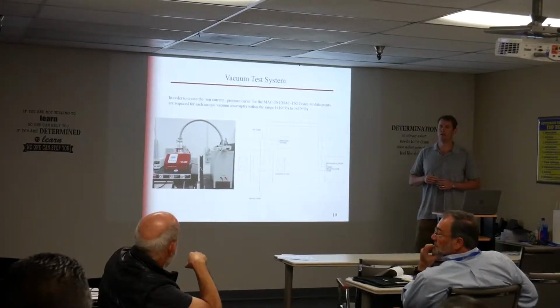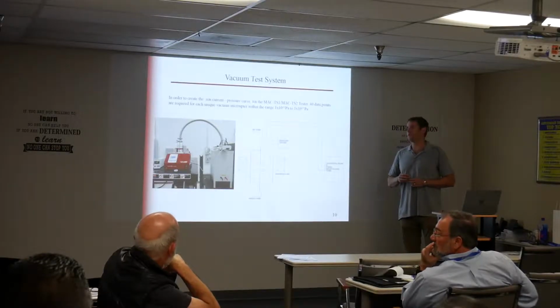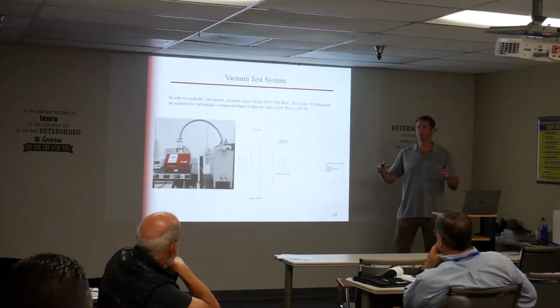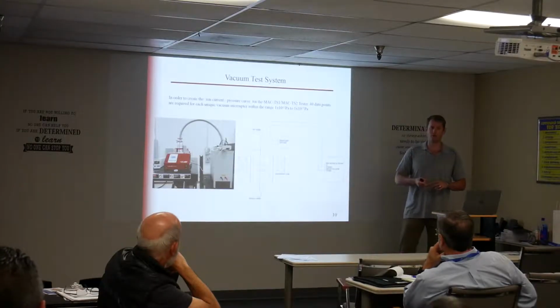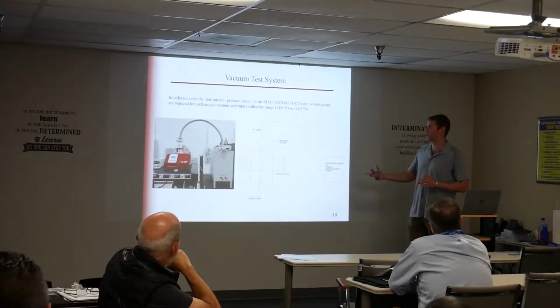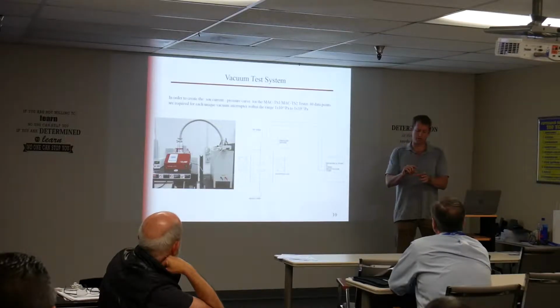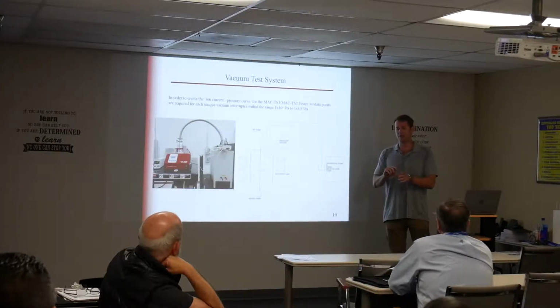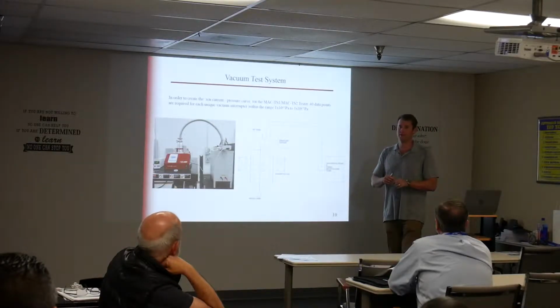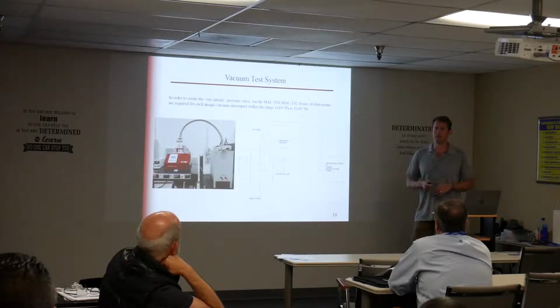In general, can you tell how old an interrupter is based on the characteristics you measure? Yeah. The size of interrupters are getting smaller and smaller because the materials, clean rooms, and manufacturing process have improved, because obviously the '80s, that was the first shot at it. And these were big glass bottles made by hand, and they have pinch tubes on these old interrupters. Where they actually puncture the bottles, suck all the air out, and crimp it and solder it. So the older bottles are a lot bigger and usually made of glass and have pinch tubes.